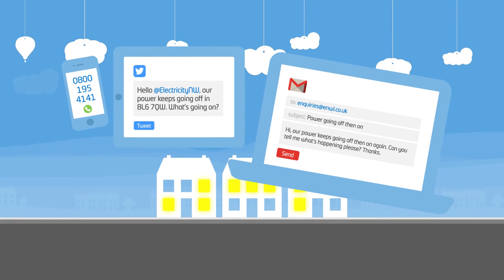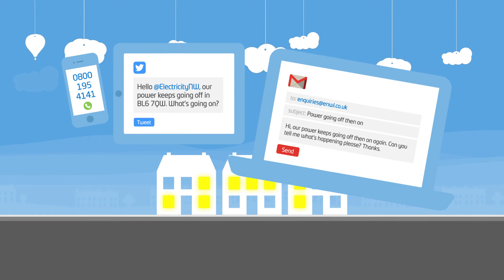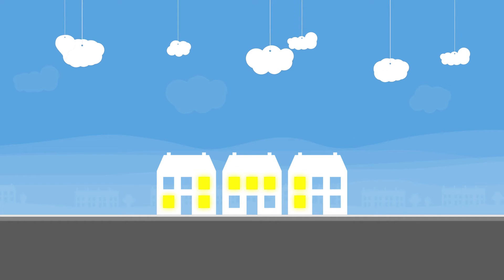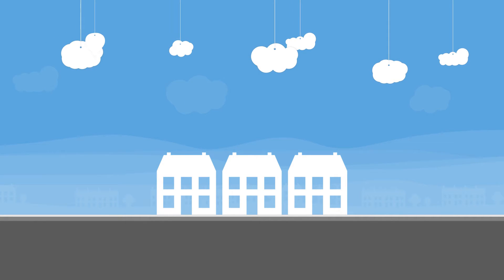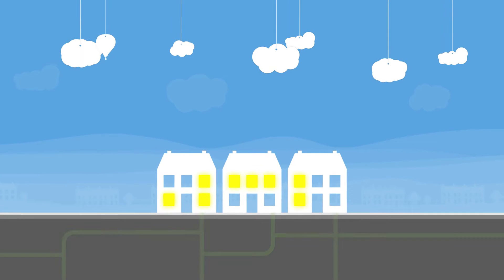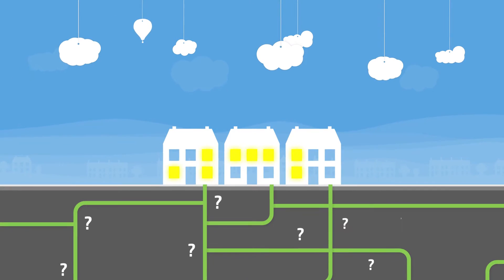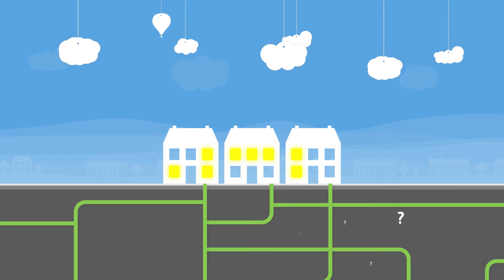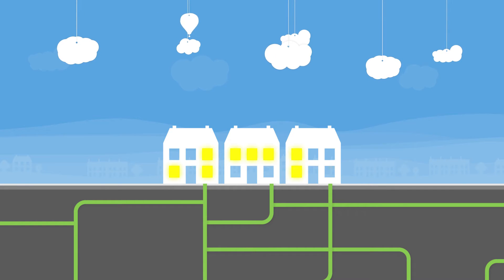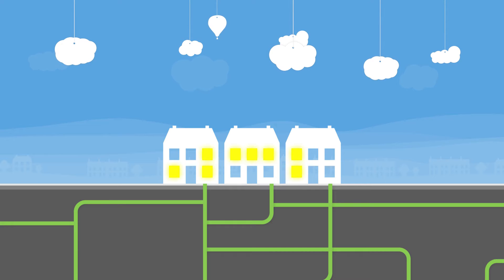There's a transient fault on the network, but what does that mean exactly? A transient fault is a fault that causes a power cut, but is no longer there when the power is restored, so it's not clear which part of the underground electricity cable needs fixing. It's also known as an intermittent fault, as you may experience a short loss of power a couple of times without any obvious cause.